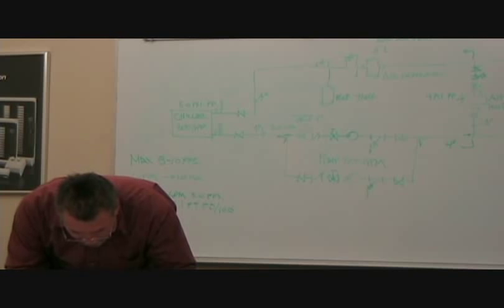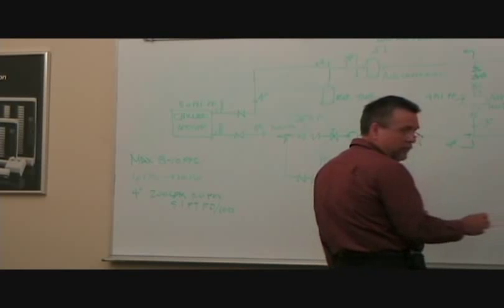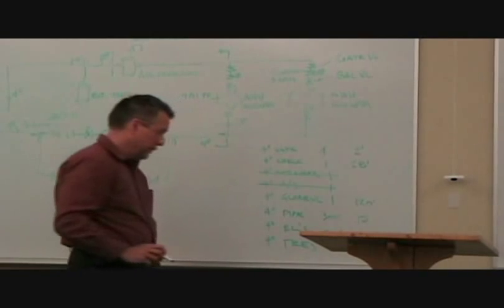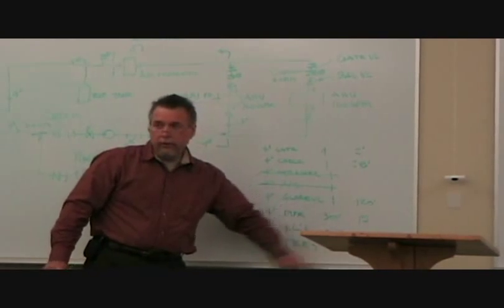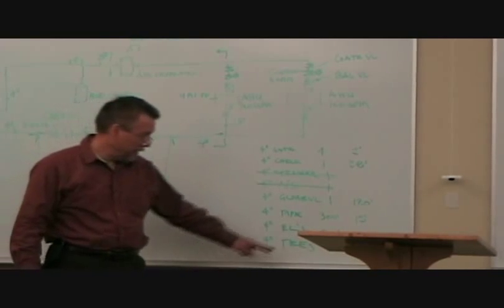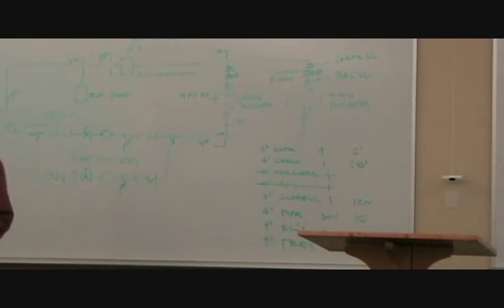Elbows, we're talking about elbows. I'm going to use a standard elbow, not a long sweep elbow, just a standard elbow. 4-inch pipe is 12 feet. So I got 20 of them, 20 times 12, 240. So all my elbows in that pipe amounted to 240 feet of equivalent length of pipe. Each elbow is equivalent to 12 feet of pipe, a stick of pipe. So not too big a deal, but some amount of deal.